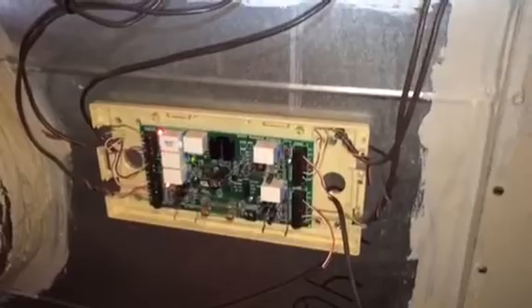I've got a normally closed damper for upstairs and a normally closed damper for downstairs. I'm not sure which side is which, but the equipment damper is the only one that's working. The thermostats are controlling the heat on and off, but they are not opening and closing the zones — so basically it's a non-zone system now.